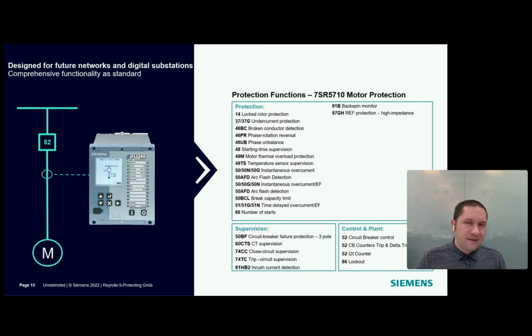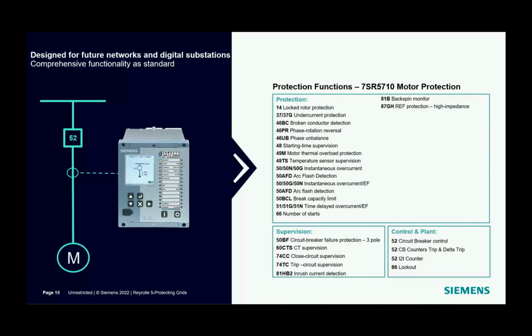Now you see a function called number of starts, which is ANSI code 66. This monitors the motor starting points. This function provides settings to control both the number of times that motor can be started within a specified time period and also the minimum time to wait between the starts. Motor starting can be inhibited, of course, when the user-defined limit is reached, depending on the motor characteristics or, let's say, thermal limitations.